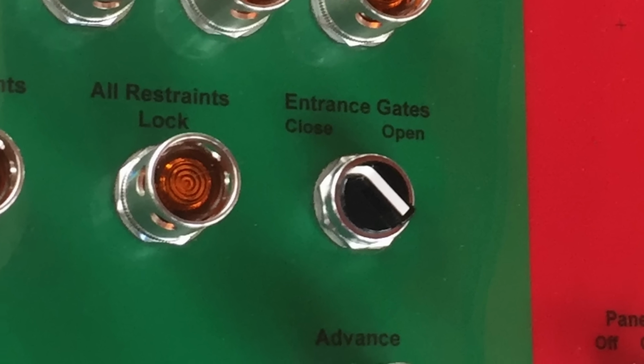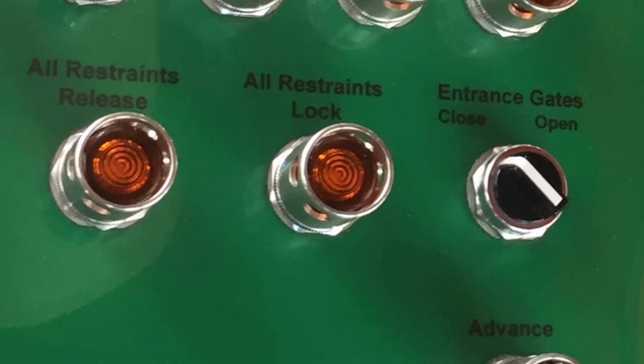Sometimes those are done in the controller to where the controller is not looking for a full signal to open or close. It just needs a momentary because the controller is sending the open and close signals. So the logic is latched one direction. So you press the button and it says close, and you press the button and then the PLC says open. And it also monitors its gates on both sides to make sure the signals match, and when it told the gates to open, they did in fact open.